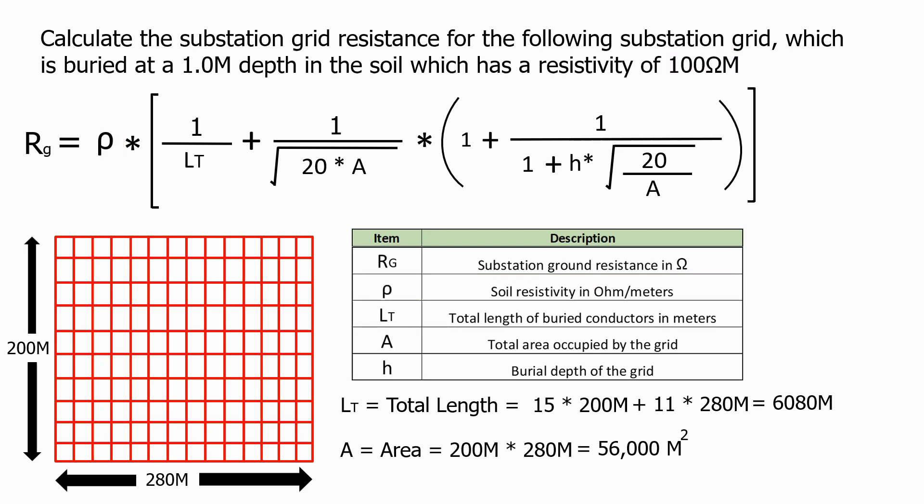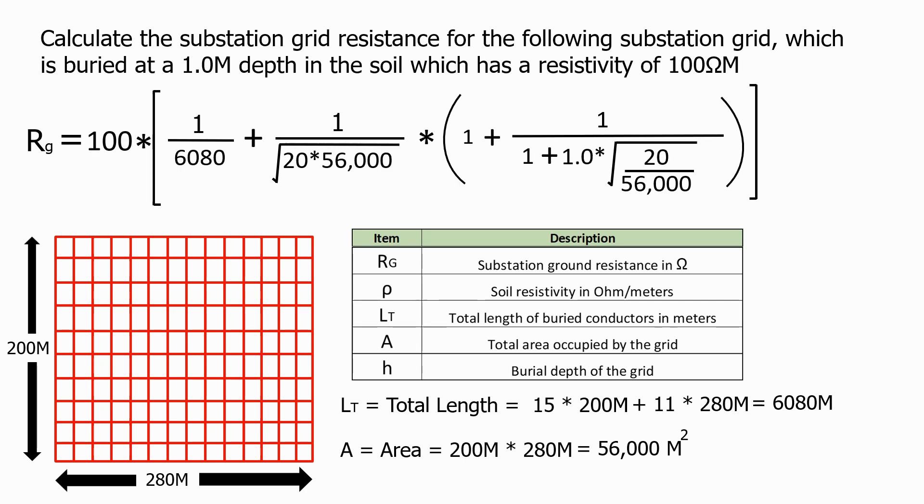Putting all these parameters into the calculation, we get a value of 0.204 ohms. What does this mean? Well, if we look remotely at the substation and attach a resistance metre, we will get a measurement of 0.204 ohms.